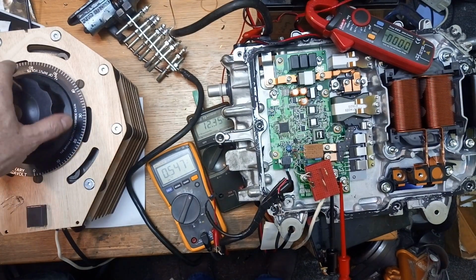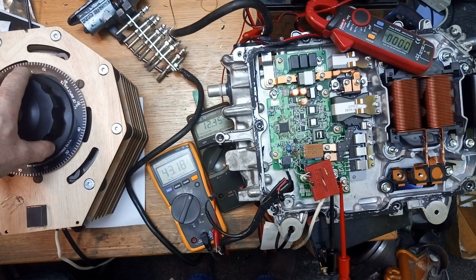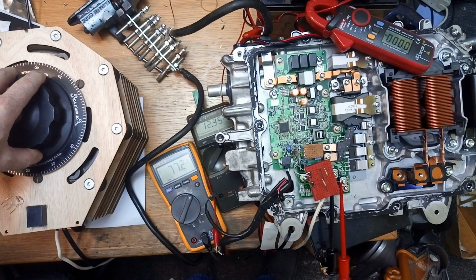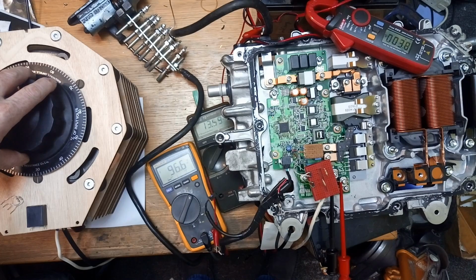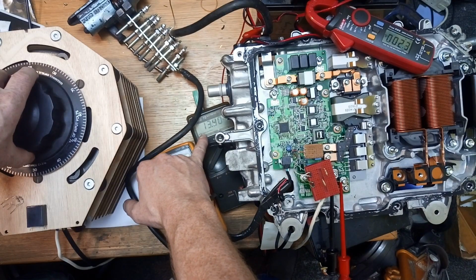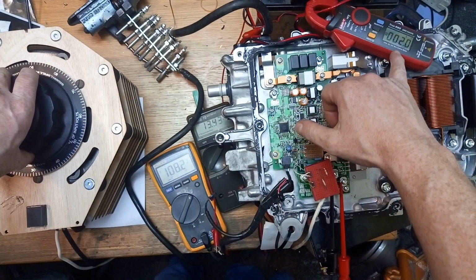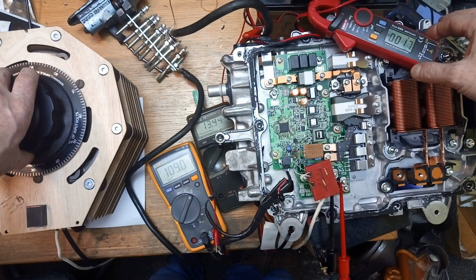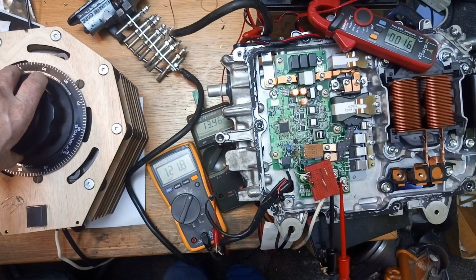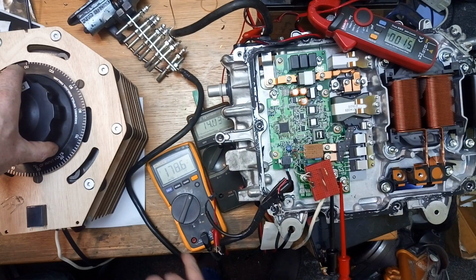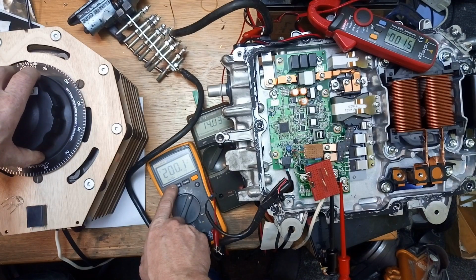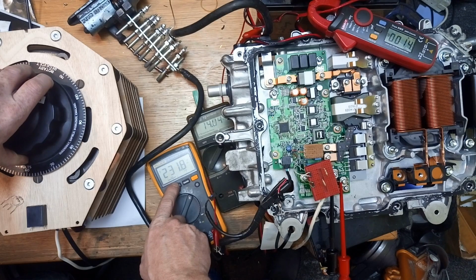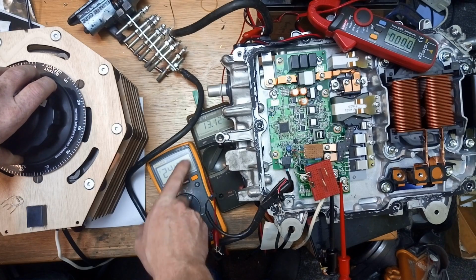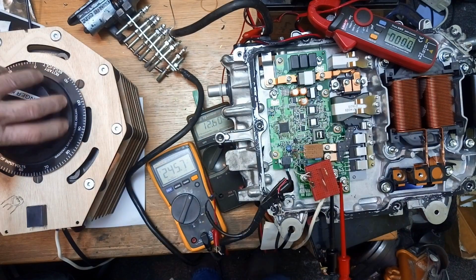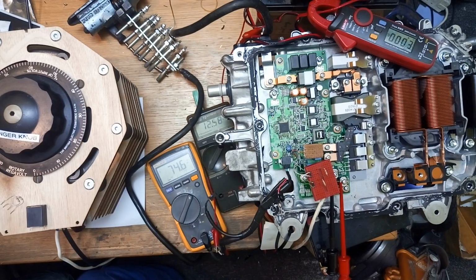Checking as standard, it should start working at about 80 volts. There it goes - the output voltage is 14 or 13.9 volts, charging the battery at about 2 amps, which is dropping. It should stop and cut out at about 235 volts. There it goes, it's switched off now, the current's gone to 0. That proves that.